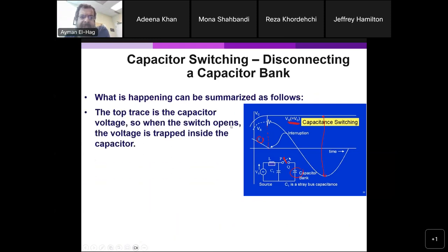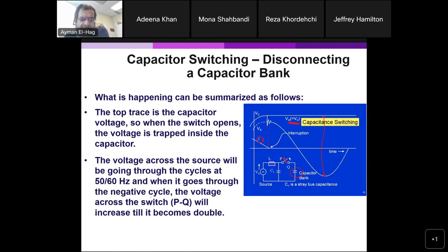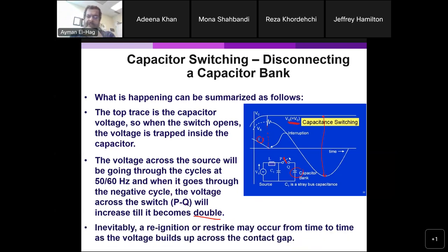Here is the summary: the top trace is the capacitor voltage with the switch open — voltage is trapped inside. The source voltage goes through its cycles, and when it reaches the negative half-cycle, the voltage across the breaker becomes double. The circuit breaker, being an open circuit, is not designed to handle such overvoltage. So re-ignition and restrike can happen inside, reconnecting and disconnecting the circuit repeatedly, leading to higher and higher voltages being built up.